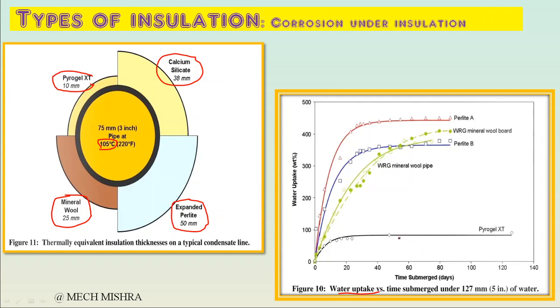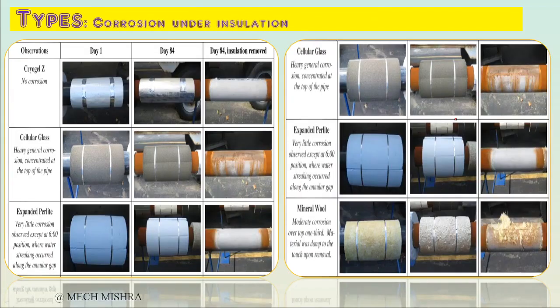So the time of the submerged days means is a type of test which has been carried out, to see how much water an insulation system can absorb. We can see the pyrogel absorbs the least water, while the perlite absorbs the maximum water. So based on that we need to design our insulation system.